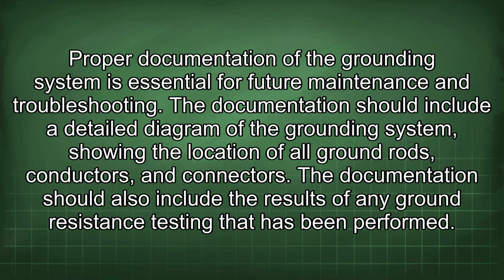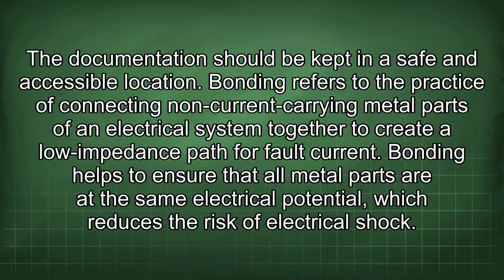Proper documentation of the grounding system is essential for future maintenance and troubleshooting. The documentation should include a detailed diagram of the grounding system showing the location of all ground rods, conductors, and connectors. Documentation should also include the results of any ground resistance testing that has been performed. The documentation should be kept in a safe and accessible location.